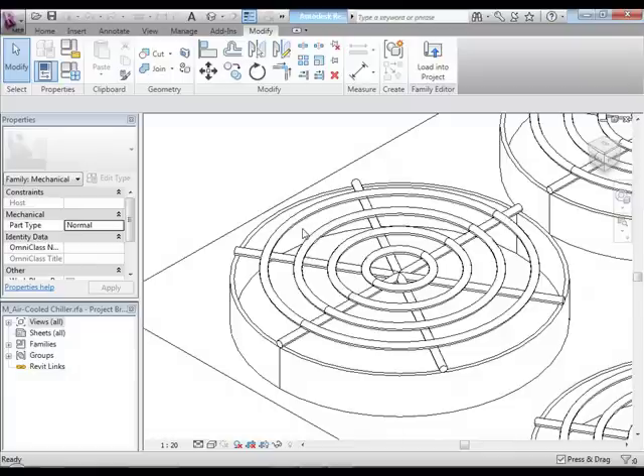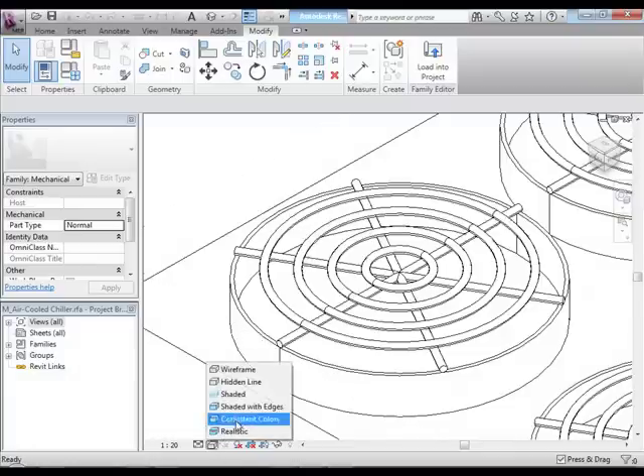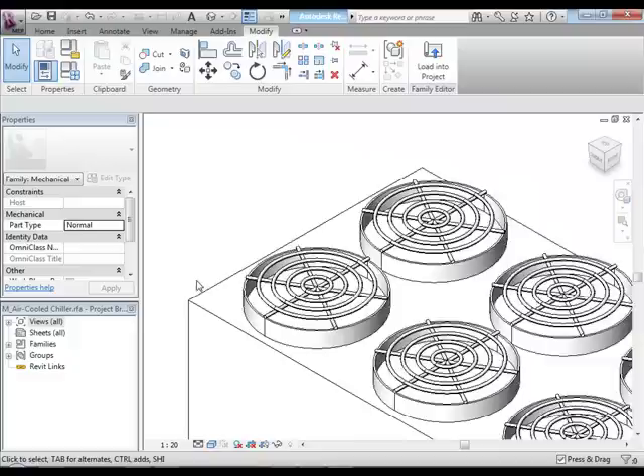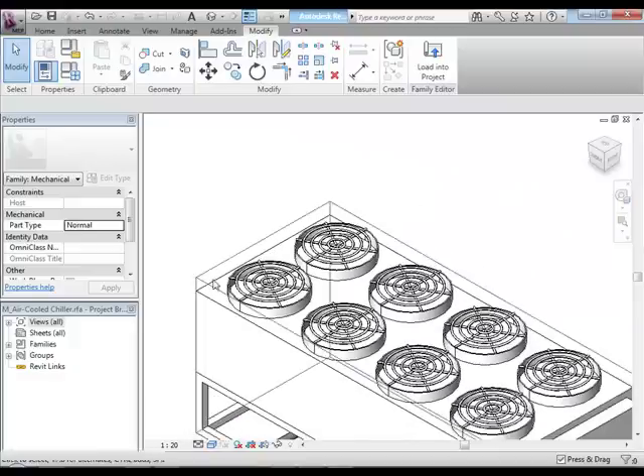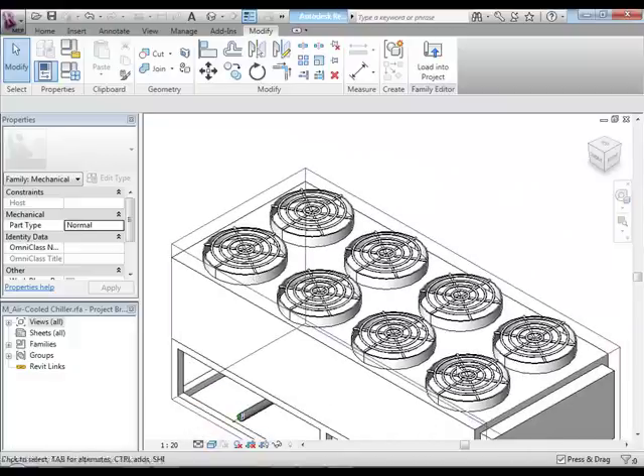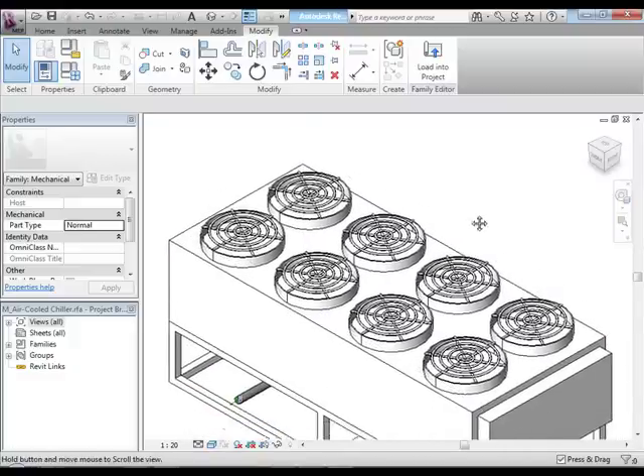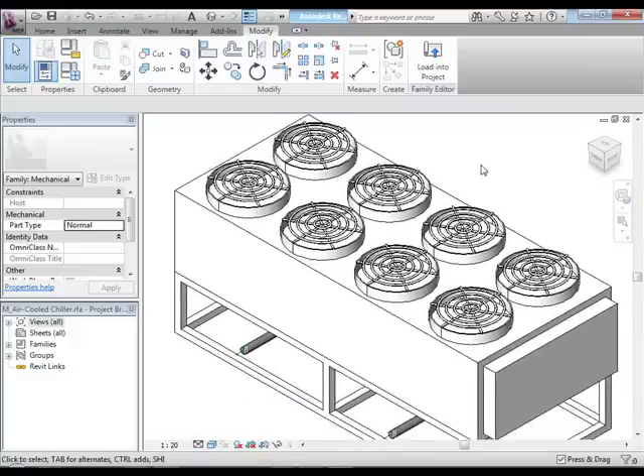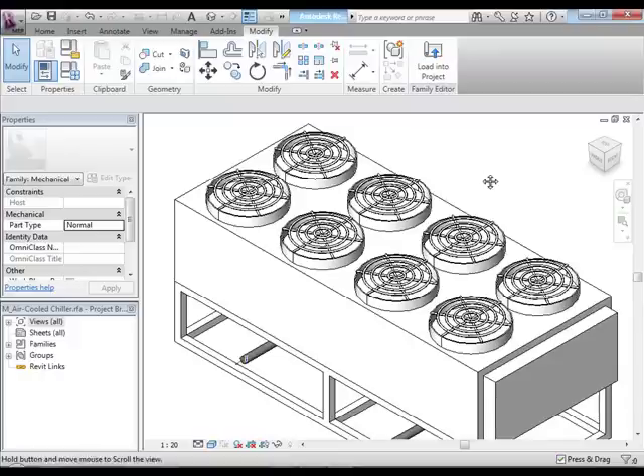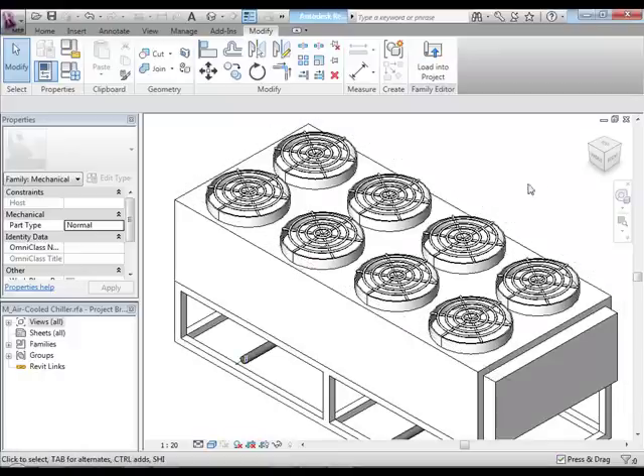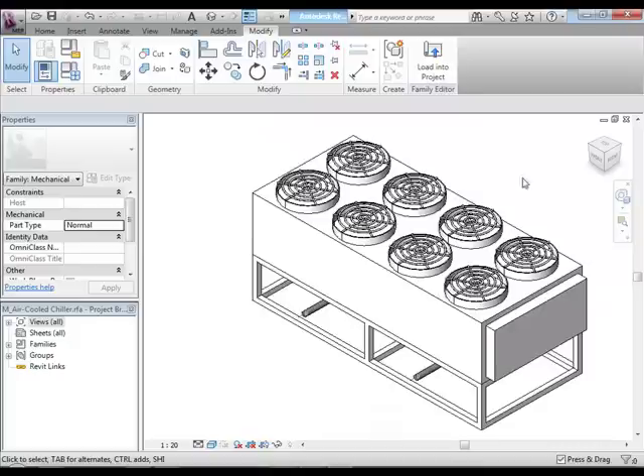Just to see how over-modeled this actually is, if we go to shaded with edges, you can see that Revit is trying to track all this geometry. We've got 8 of those times however many units we put in the file, it's going to start bogging Revit down. How do we fix that? We just create simple geometry and draw over it with detail lines or model lines.